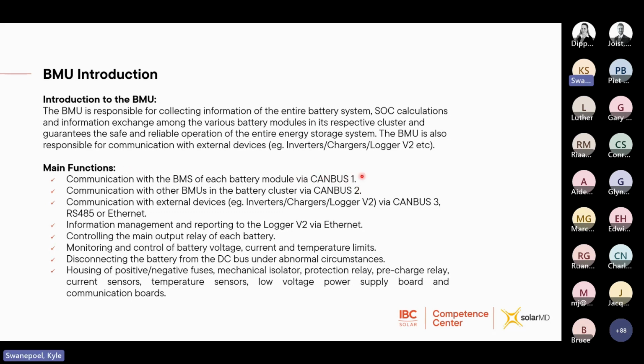As I mentioned in the beginning, with the different communication ports on the BMUs, the CAN bus 1 is reserved for internal communication for that battery to its battery modules. The CAN bus 2 is used to communicate between BMU to BMU so that they can share their relevant battery information with each other. And then CAN bus 3 and RS485 or Ethernet is used to communicate this information to external devices. And then the information management and reporting will be done to the Logger V2 via Ethernet.